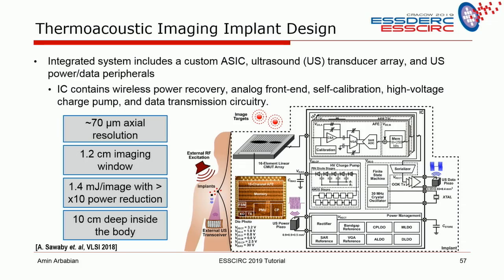The energy usage per frame for an image is substantially higher than what we had before, because of the complexity of the system: 1.4 millijoule per frame. So we're improving that in the next batch. A lot of that actually went into our memory system. It wasn't designed the way it should have been, probably, and it operates about 10 centimeters in tissue.